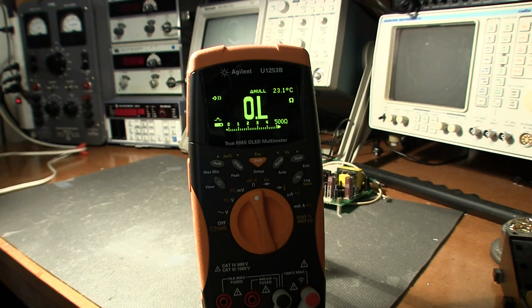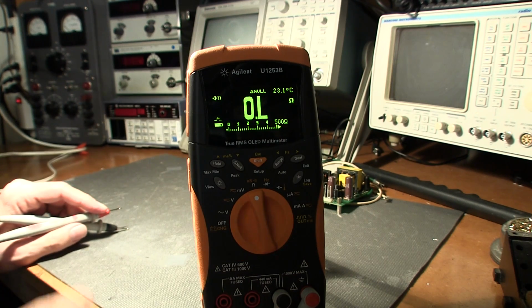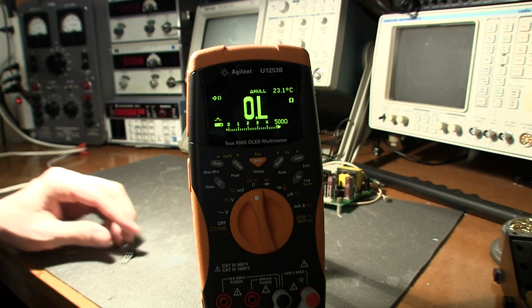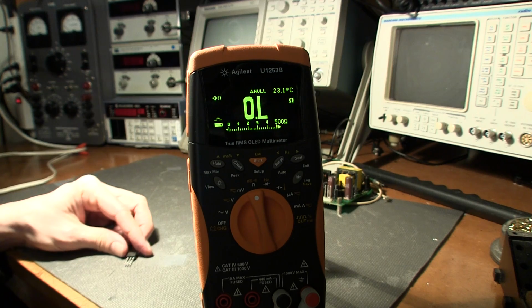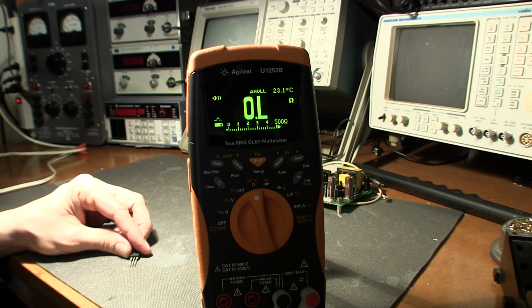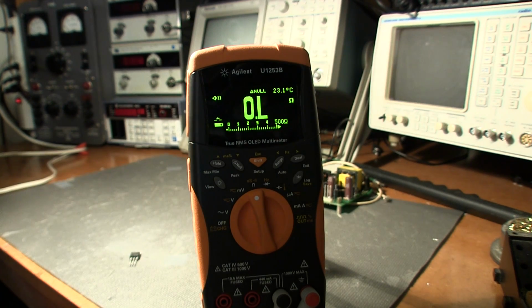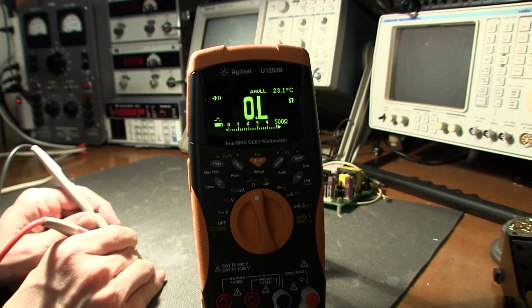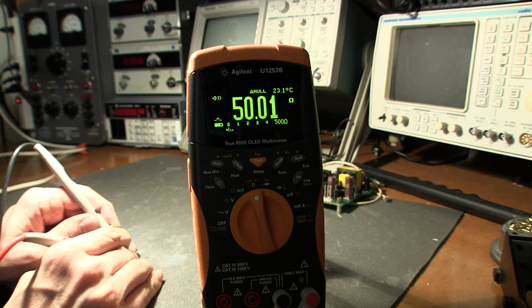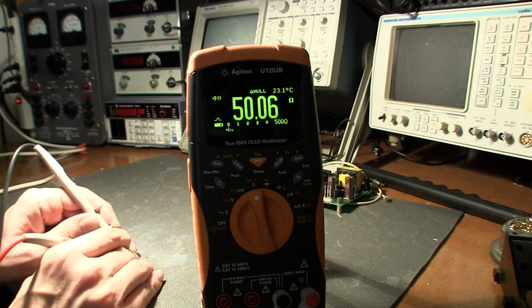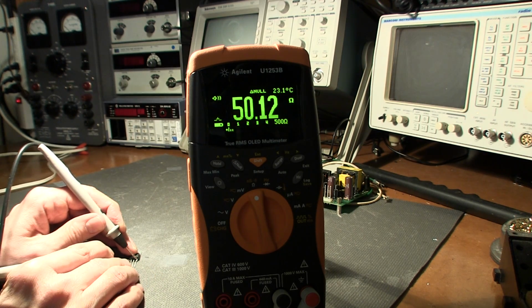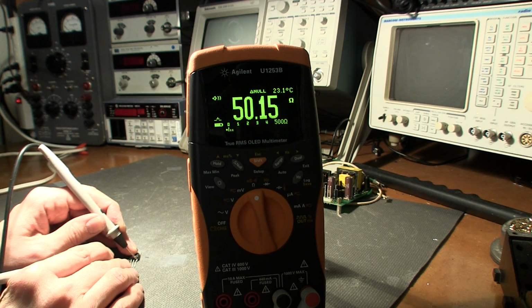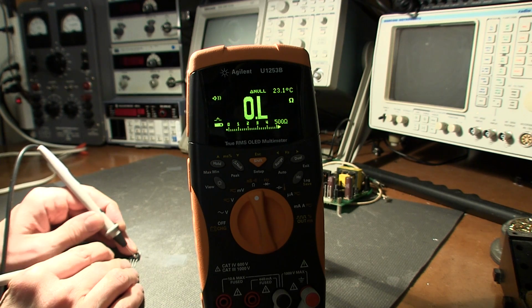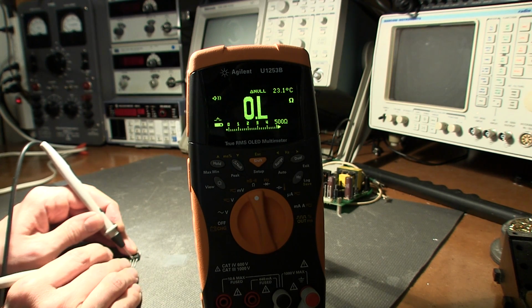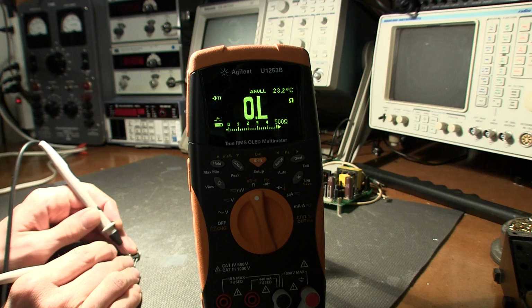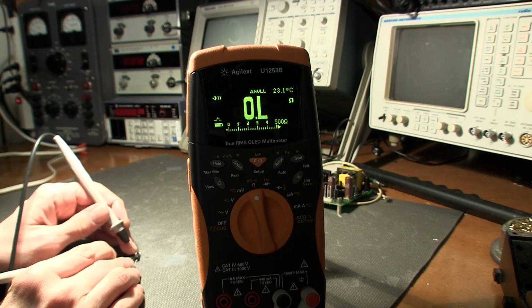Now, here's something interesting for those of you that may not play with SCRs a lot. We're going to test from the gate to the cathode on a brand new device, and this is what we get: 50 ohms. That's normal. No matter which way you put the leads, you're going to get 50 ohms from the gate to the cathode. On the continuity mode, if you test from the anode to the gate or the anode to the cathode, you're going to get nothing, no matter which way you put the leads.